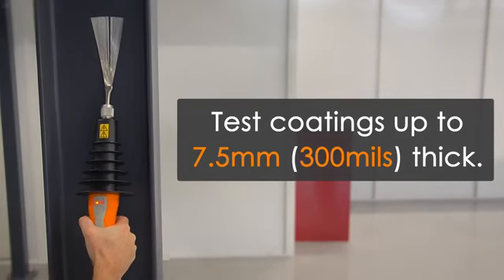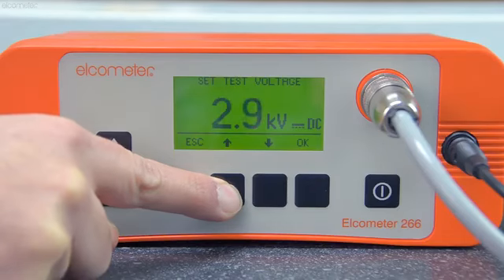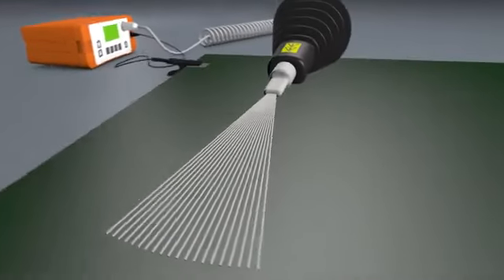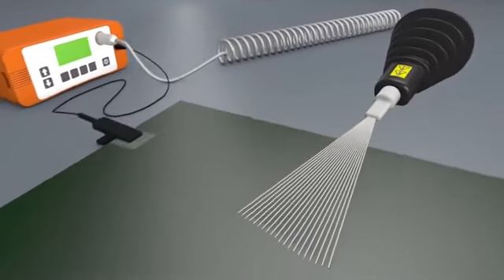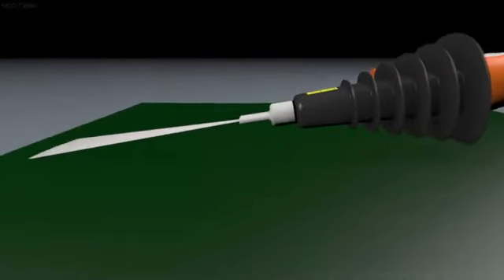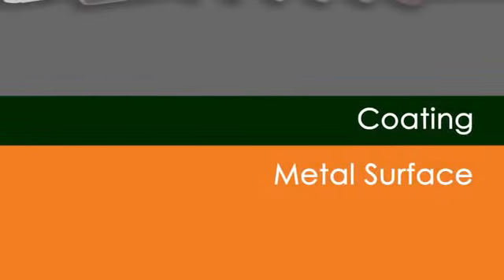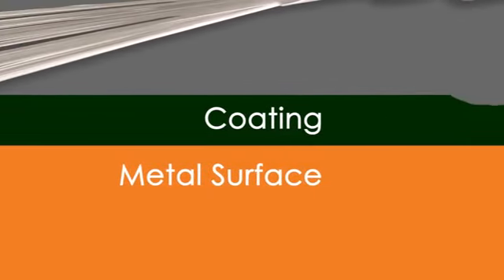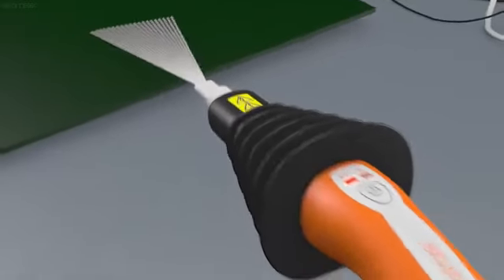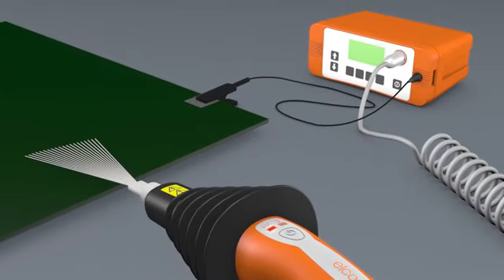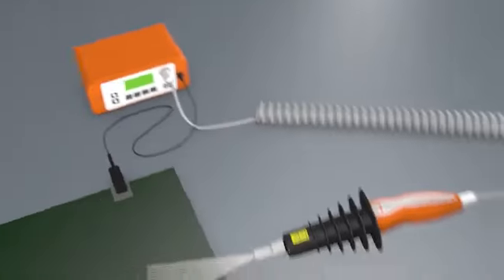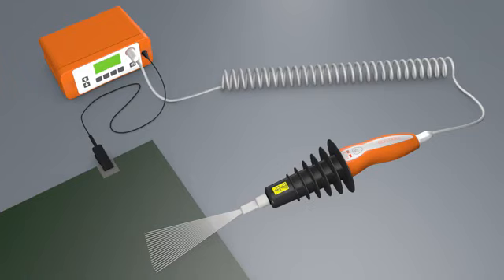So, how does it work? Put simply, a high voltage of between 0.5 and 30 kV is applied to a probe. The probe is then passed over the coated surface. The voltage to the probe is constant, hence the name continuous DC. The voltage used should be high enough so that in areas where the coating is electrically weaker due to a flaw or discontinuity, there is sufficient voltage to break down the gap between the probe and the substrate. When this breakdown occurs, the current flows from the probe, through the substrate, and back into the holiday detector, via a grounding cable which is clipped to an uncoated section of the substrate being tested, completing a circuit. This instantly triggers an alarm to signal a flaw has been detected.